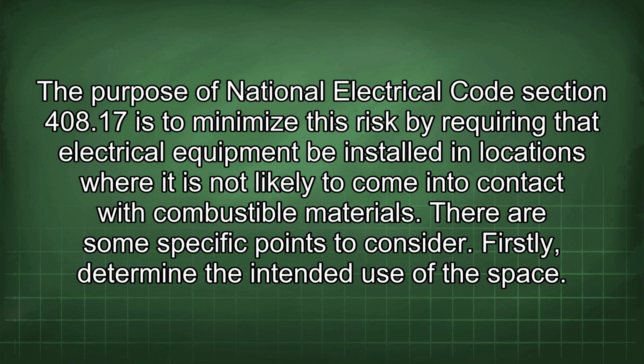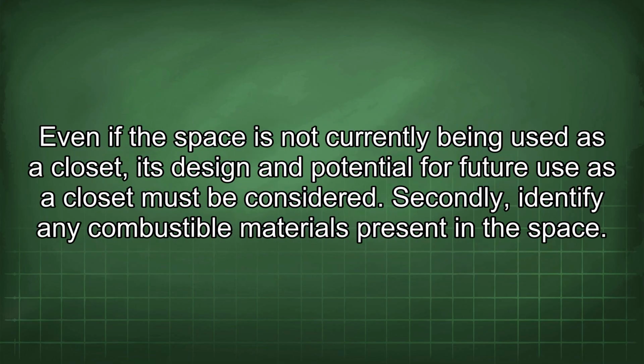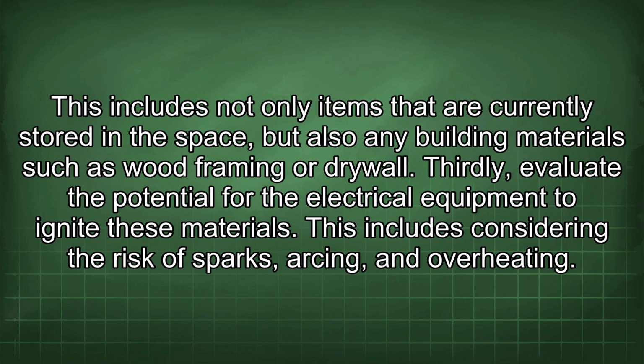The purpose of National Electrical Code Section 408.17 is to minimize this risk by requiring that electrical equipment be installed in locations where it is not likely to come into contact with combustible materials. There are some specific points to consider. Firstly, determine the intended use of the space. Even if the space is not currently being used as a closet, its design and potential for future use as a closet must be considered. Secondly, identify any combustible materials present in the space. This includes not only items that are currently stored in the space, but also any building materials such as wood framing or drywall. Thirdly, evaluate the potential for the electrical equipment to ignite these materials.